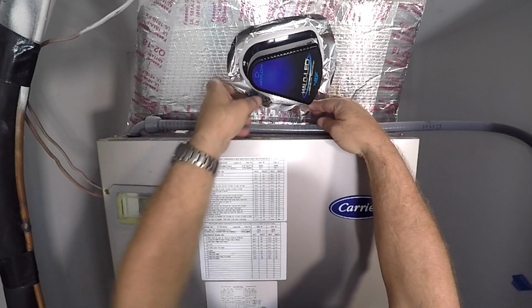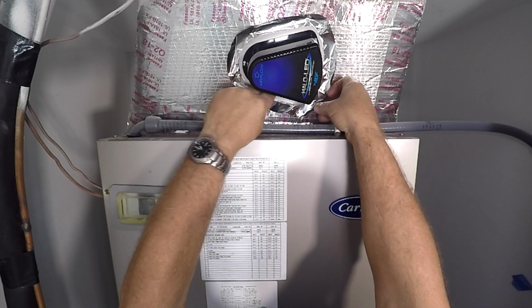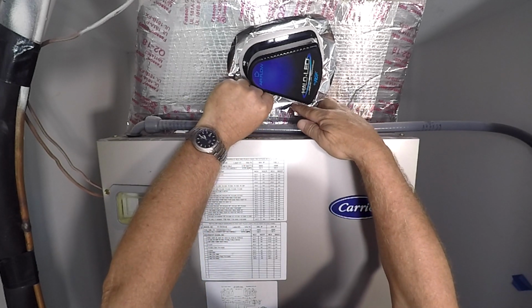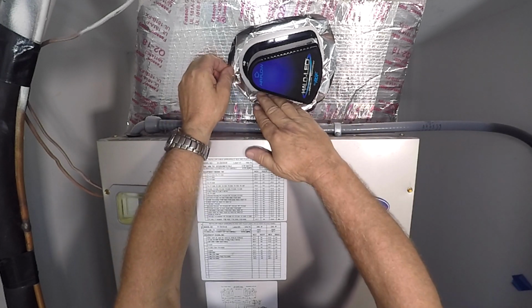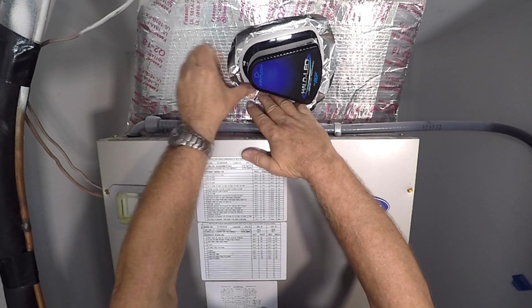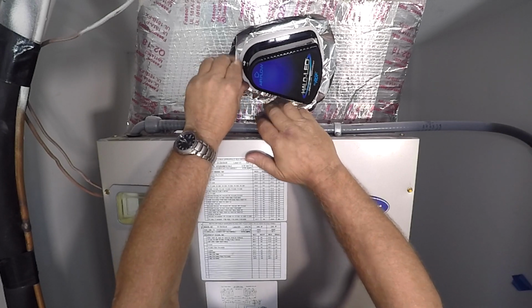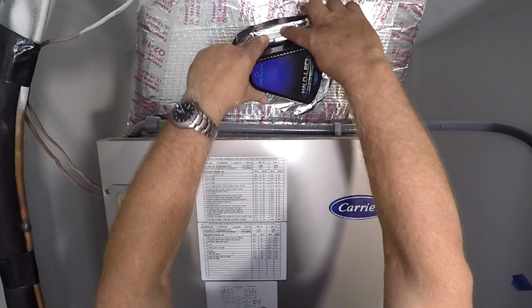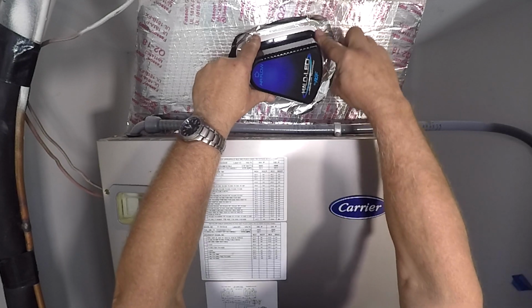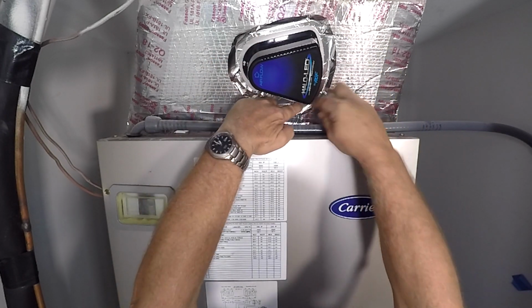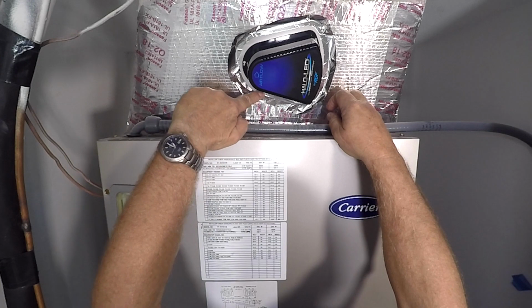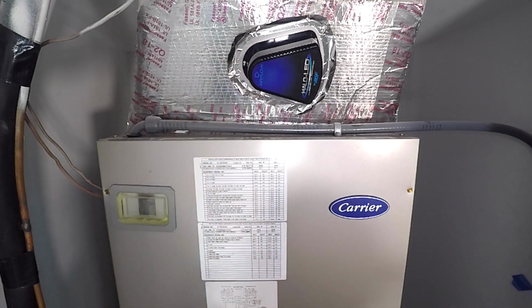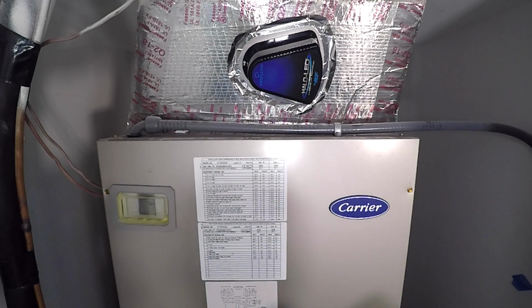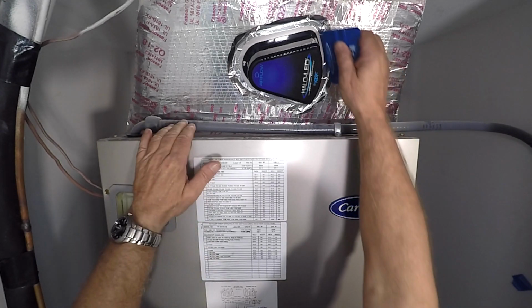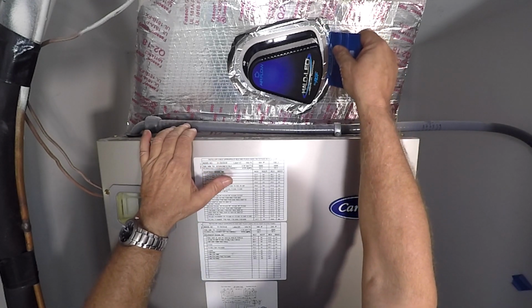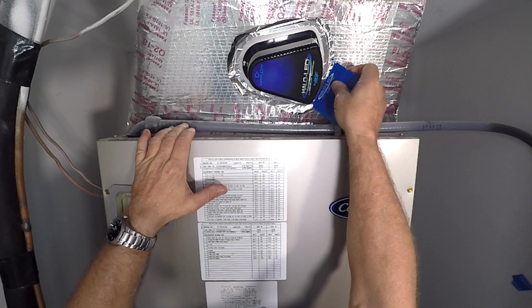In all instances, it is much preferred to have the unit installed in the supply. However, when that is prohibitive, that you cannot physically fit it into the supply, then you can mount it in the return. You will lose a slight amount of efficiency of the unit doing such. But again, if you have no room to install the unit into the supply, then it must go in the return.